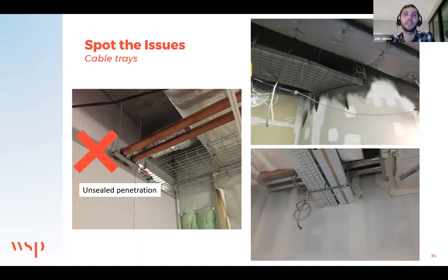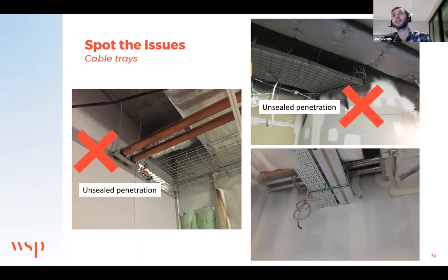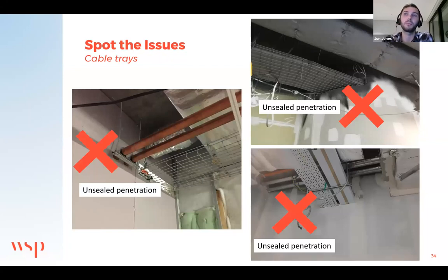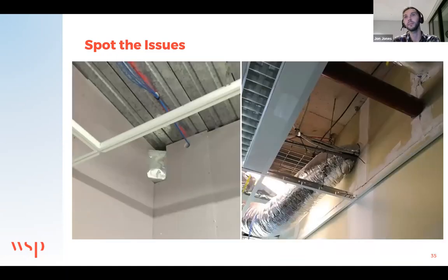Unsealed penetration, that's going to be bad. Looking at the others, again, you've got the same details really. If you've got a cable tray going through here, it needs to be filled and sealed up better to maintain the acoustic integrity of a partition. We don't want to see daylight or have big holes through walls if there's a requirement for privacy or acoustic separation between those spaces.